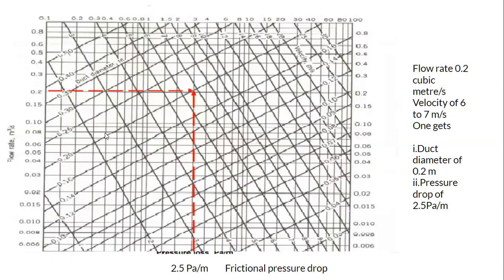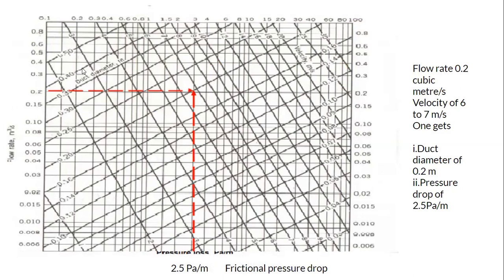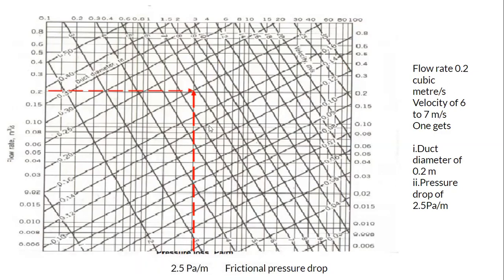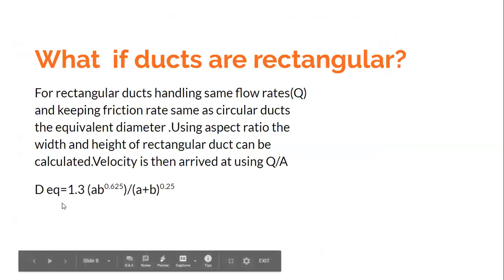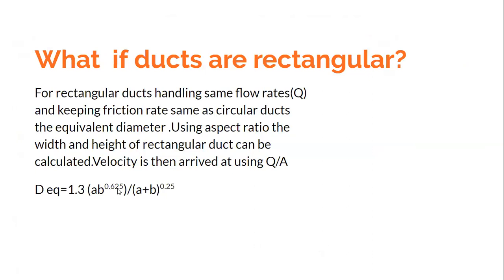For example, suppose I want to design a duct with a friction drop of 2.5 Pascals per meter and a flow rate of 0.2 cubic meters per second, and I am supposed to use a rectangular duct. From the circular duct chart, I get an equivalent diameter of 0.2 meters. I am not going to choose a rectangular duct with both width and height of 0.2 meters. Instead, I use the empirical relation for equivalent diameter.